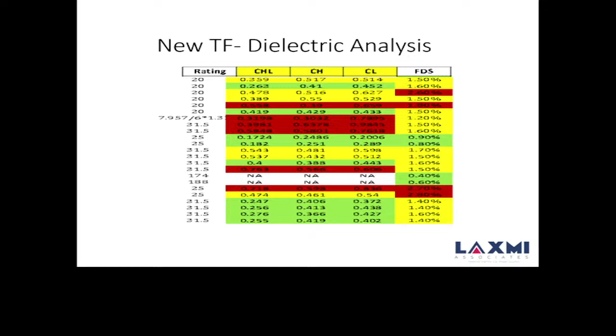So once this is confirmed, what you are seeing here is a very standard benchmark. Standards are there, IEC, IEEE, CIGRE, and all have their own benchmarking, and from there this is a derivative: less than 1% is good, 1 to 2% is dry, and 2 to 3% is moderate, like that. It is defined in different standards.